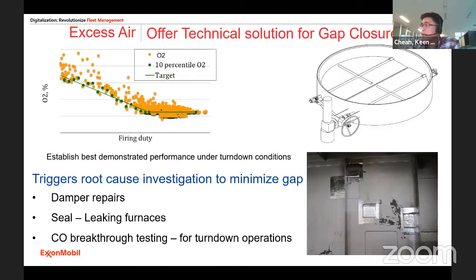And beyond a certain point, there is difficulty keeping the excess O2 low. So as we derate, the burner's performance goes down as a function of the design, and excess O2 goes up. But what this tool helps to identify is really what should those excess O2 targets be, and what is that achievable point that I have managed to achieve in the past?